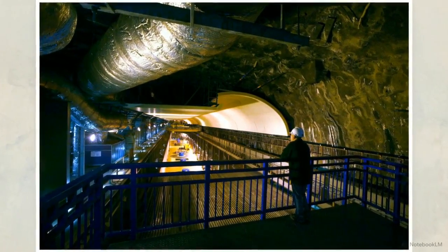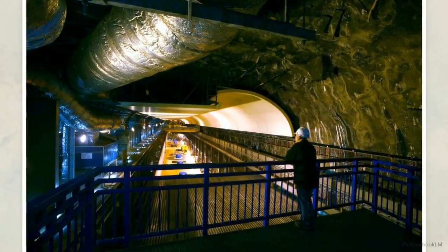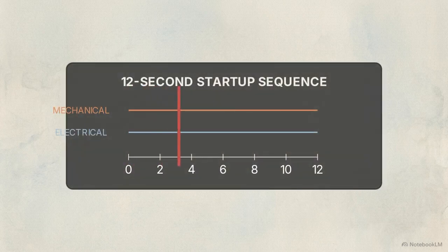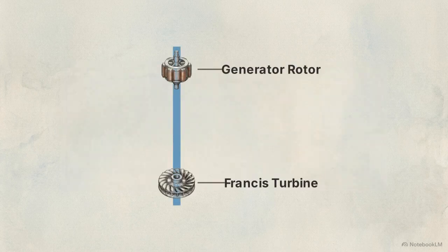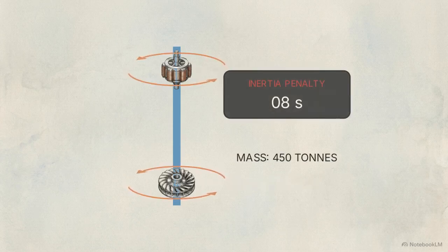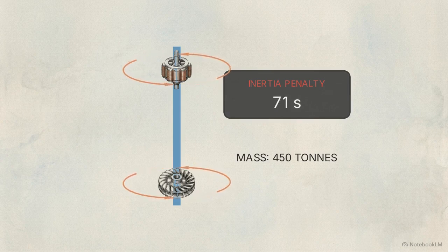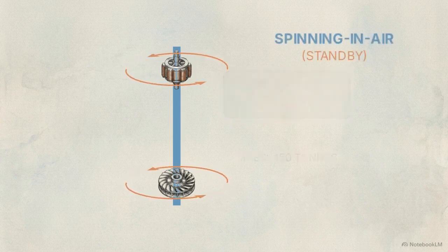The facility operates as a highly optimized electromechanical conversion system. To isolate exactly how it achieves this response time, we have to freeze the operation and break down the specific electrical and mechanical sequence occurring within that 12-second window. This diagram shows a stationary Francis turbine and its attached generator rotor. At a complete standstill, initiating the rotation of a 450-ton steel mass takes 71 seconds just to overcome physical inertia.